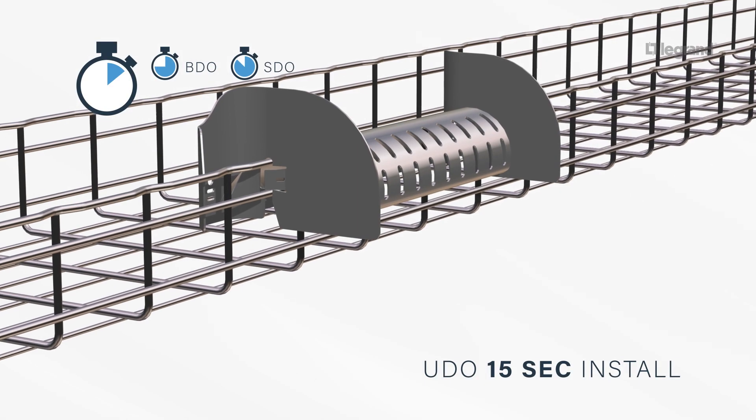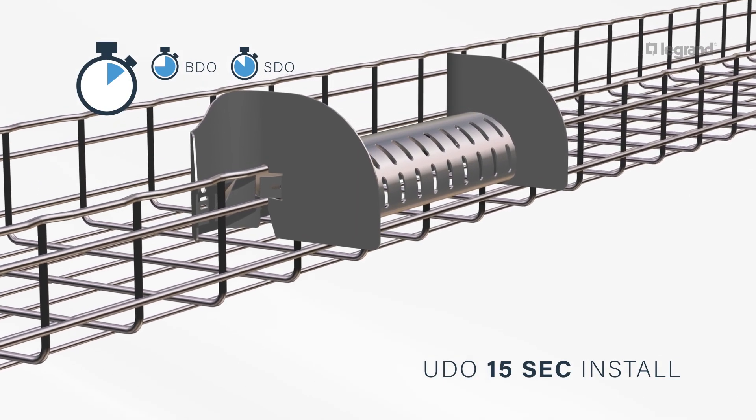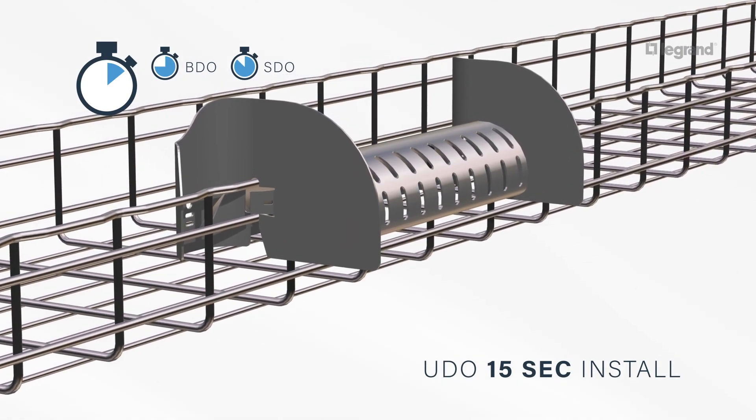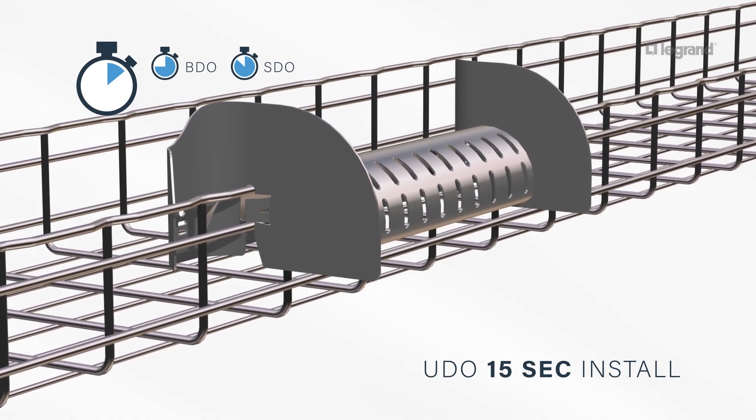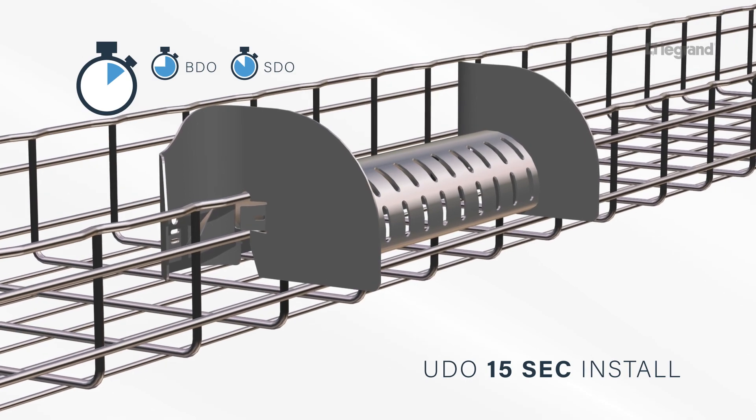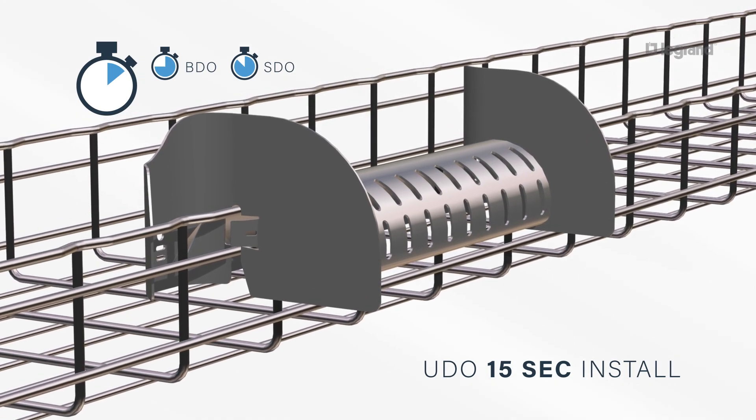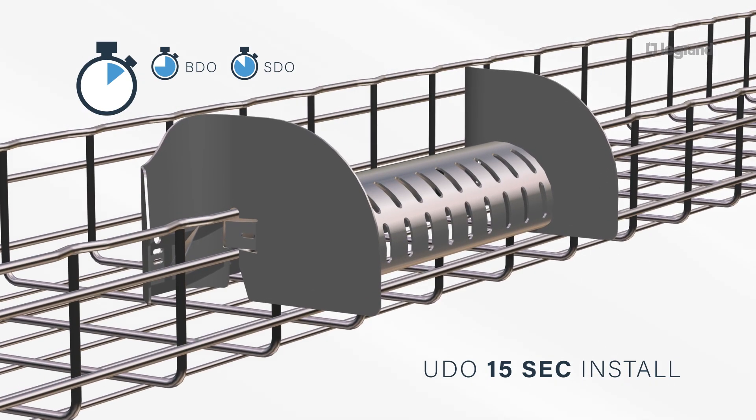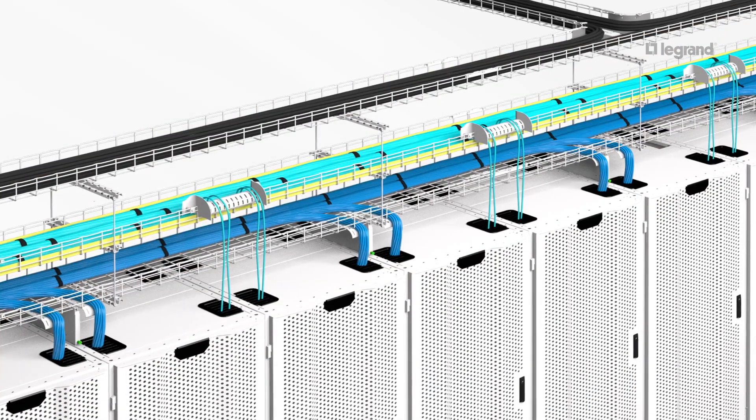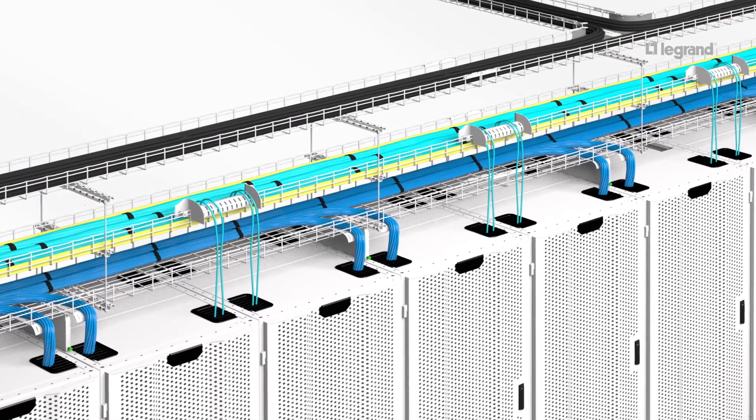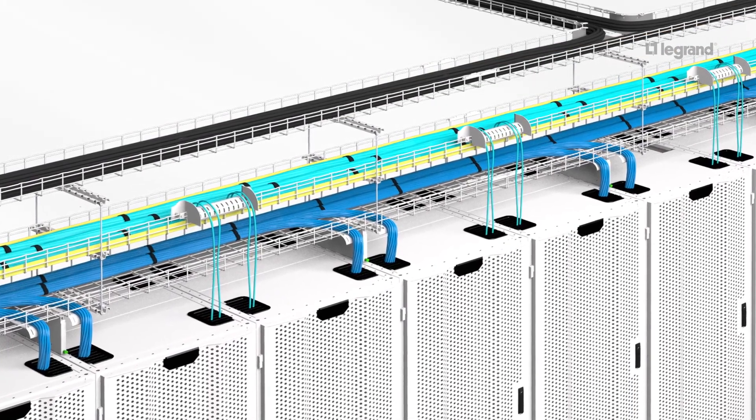The UDO dropout sits on the top rail for easy installation without cutting or modifying tray, and it does not decrease tray strength. The no-hardware bend-over tab design allows for easy installation. The UDO dropout can be reused when data center is reconfigured.